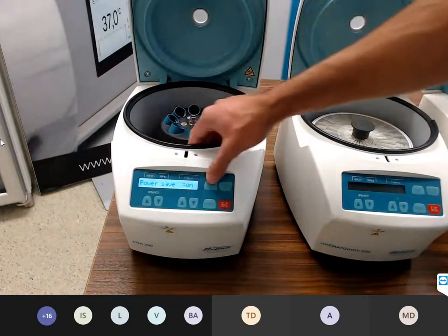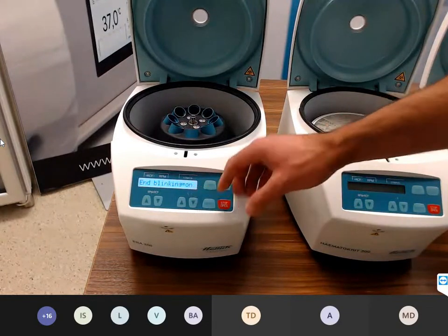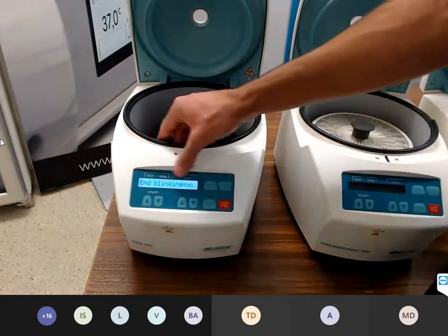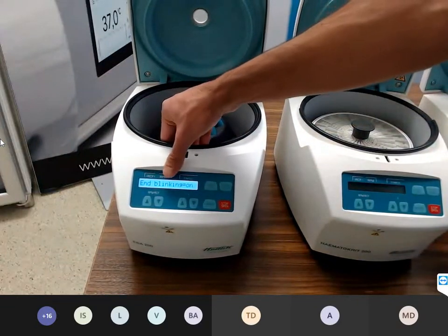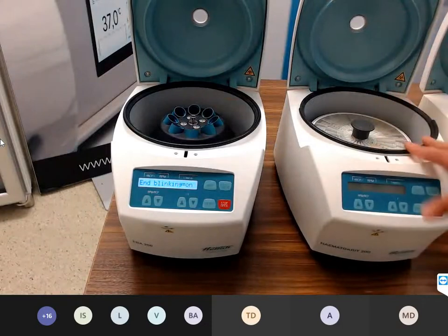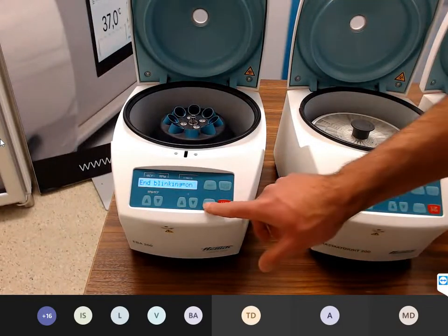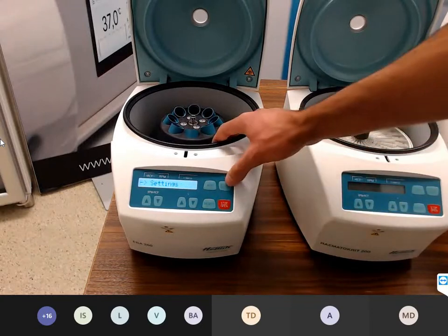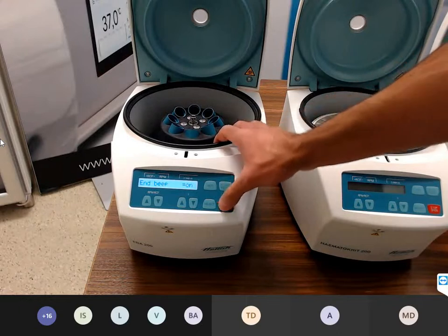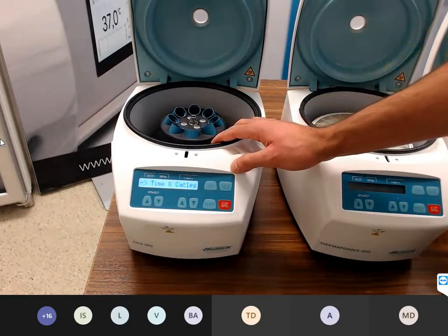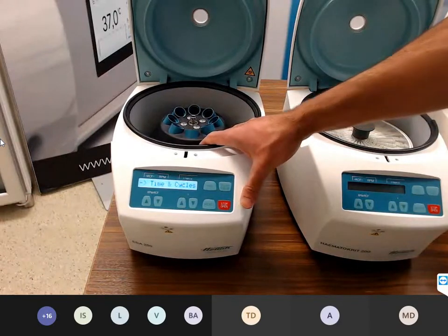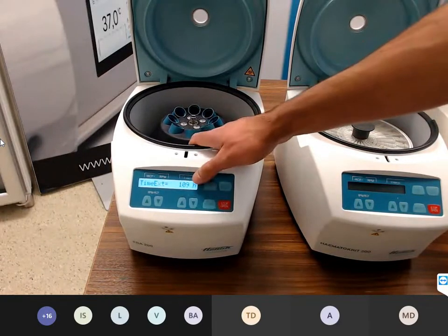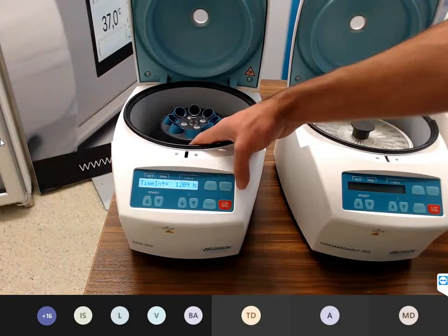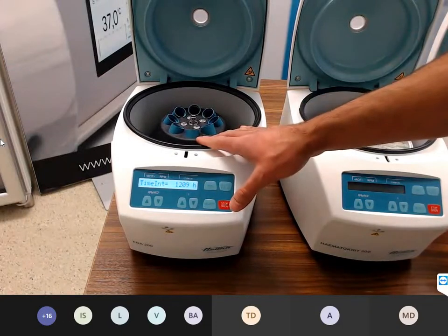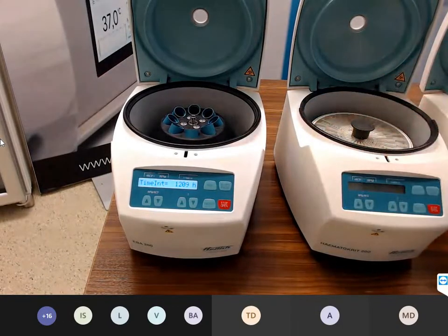Power save is for the background light. The blinking is the same as the acoustic signal. You can see the visual signal also on the display. The display is blinking in case of an error or after each run. The next is the time and cycles. It's an important thing. You can read the external time and the internal time. The external time is the time of the centrifuge, and the internal time is the running time.